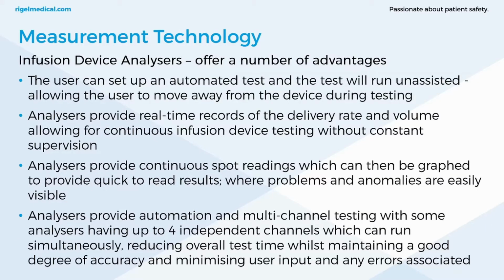So measurement technology, infusion device analyzers, they offer a number of advantages. The user can set up an automated test and the test will run unassisted. This allows the user to move away from the device during testing. It's not like the other methods where you've got to continuously check on the device and there's all sorts of issues that can occur. With this, it runs completely automated. They also provide real-time records of delivery rate and volume. It allows for continuous infusion device testing without constant supervision. They provide continuous spot reading, which can then be graphed to provide quick-to-read on-screen results. And with this, problems and anomalies are easily visible.